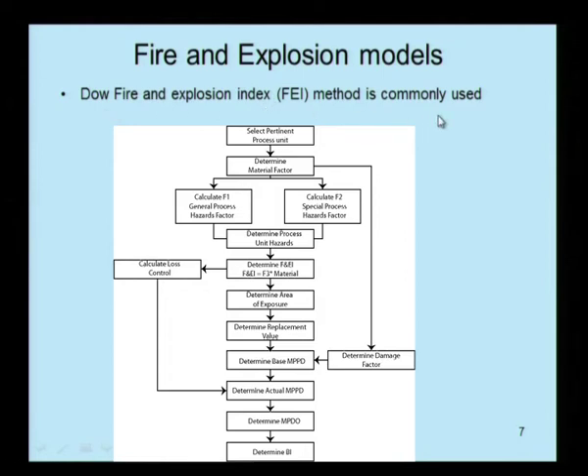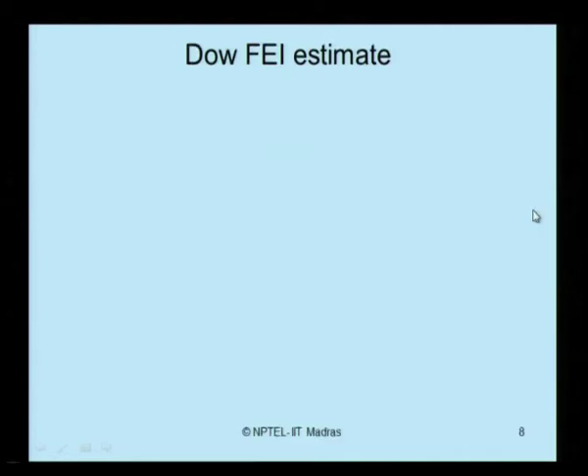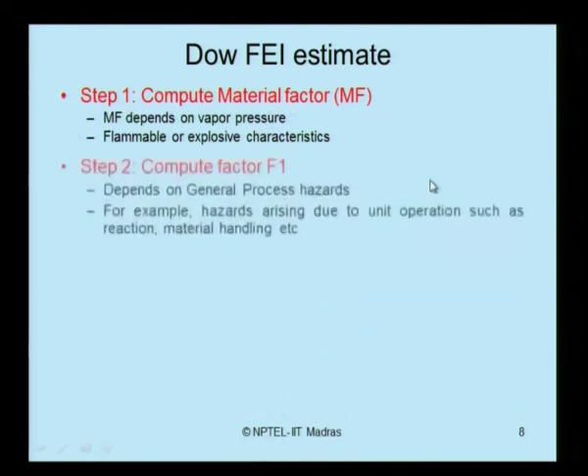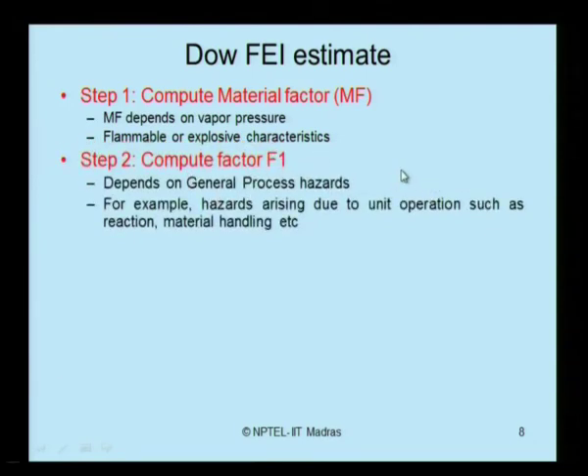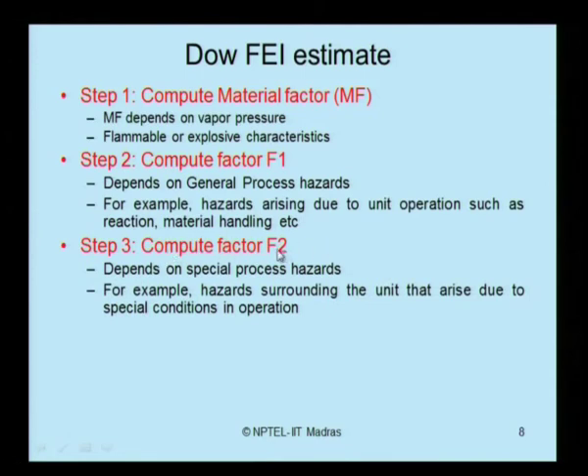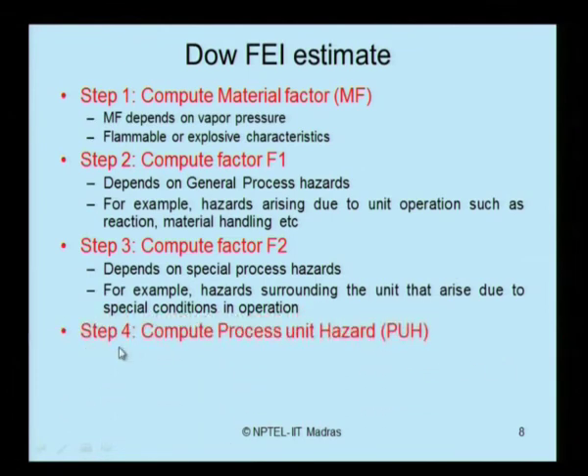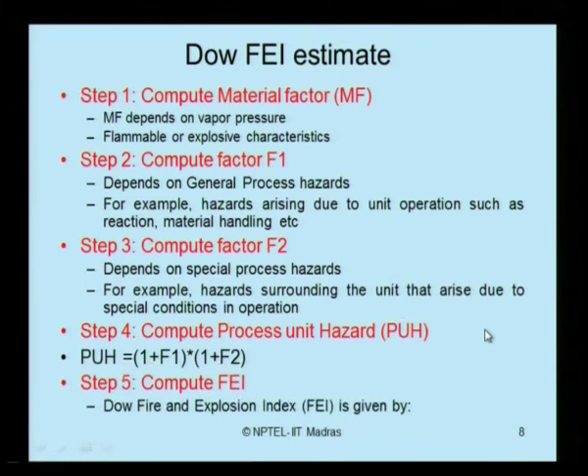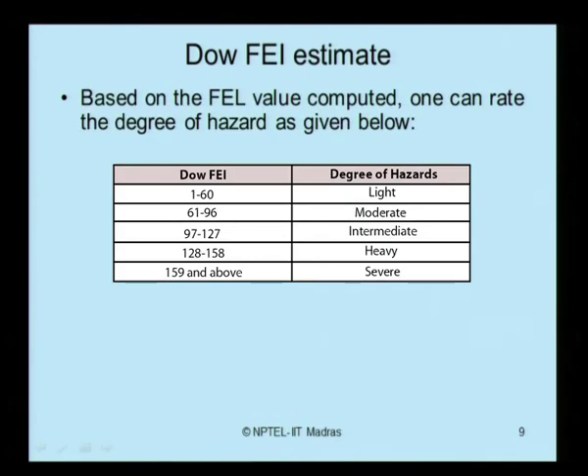The Dow Fire and Explosion Index (FEI) method is commonly used for fire and explosion models. The flowchart to compute FEI is as follows: Step 1 — compute the material factor, which depends on flammability and explosive characteristics. Step 2 — compute factor F1, which depends on general process hazards such as unit operations like reaction and material handling. Step 3 — compute factor F2, which depends on special process hazards arising from special conditions in operation. Step 4 — compute the Process Unit Hazard (PUH), given as (1 + F1) × (1 + F2). Finally, compute the Dow Fire Explosion Index as: material factor × PUH.